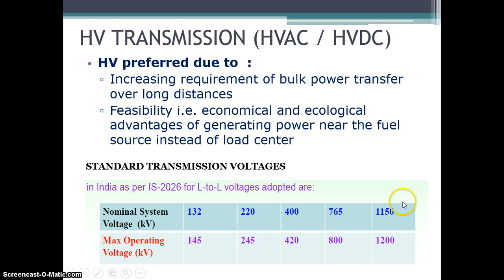The power handling capacity of a line is defined by 0.5 V square divided by X into D. This formula comes as 0.5 because it is sine 30. So the maximum consideration for power angle is 30 degrees. In V square, we have assumed that the receiving end and sending end voltage magnitudes are nearly equal. So V square sine delta divided by X. You have studied the same formula in your elementary power system classes.